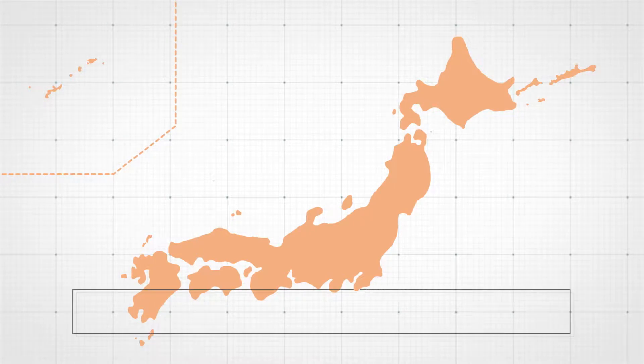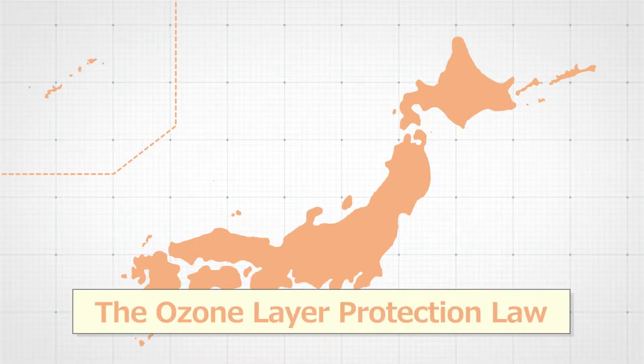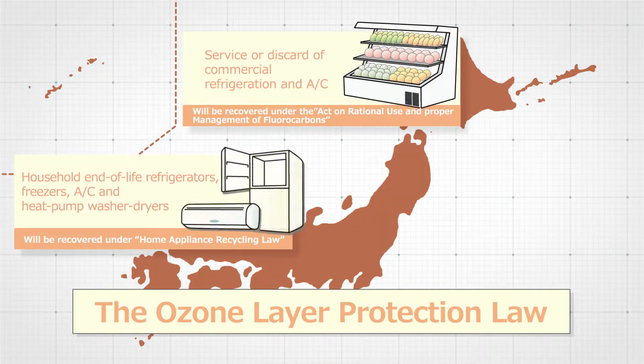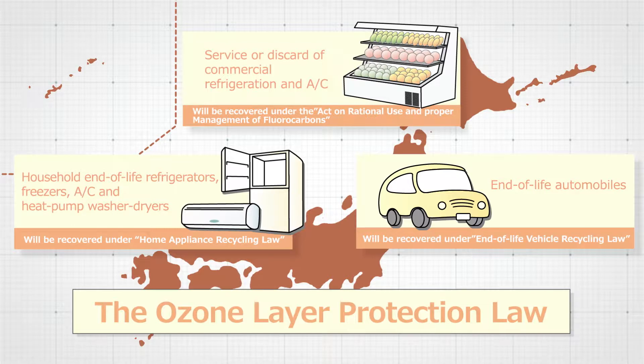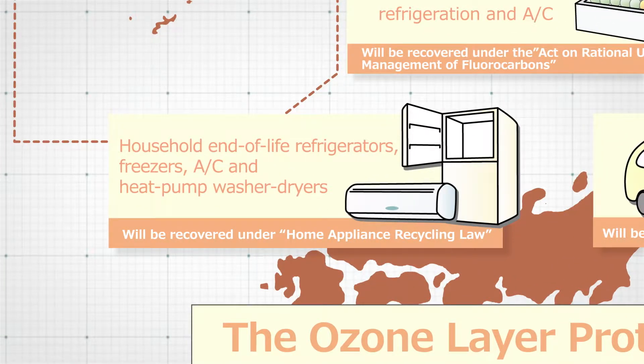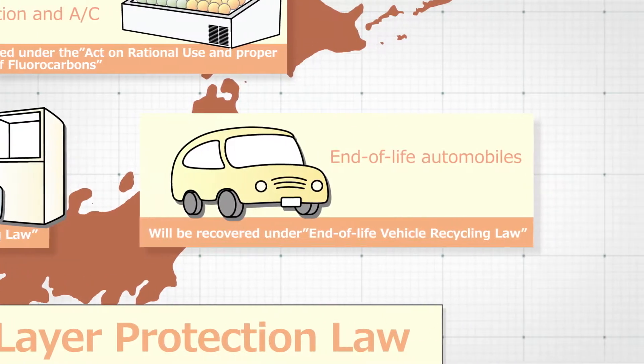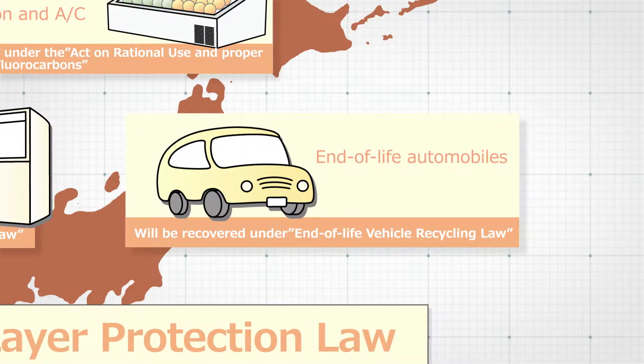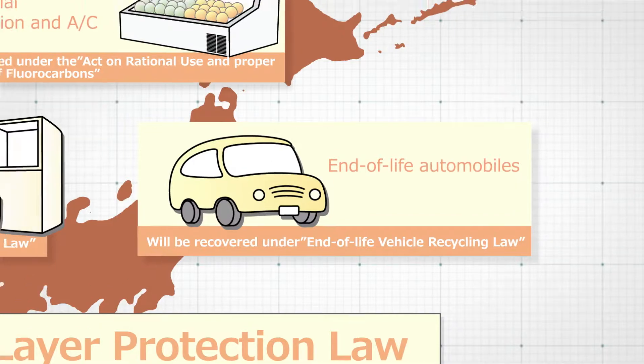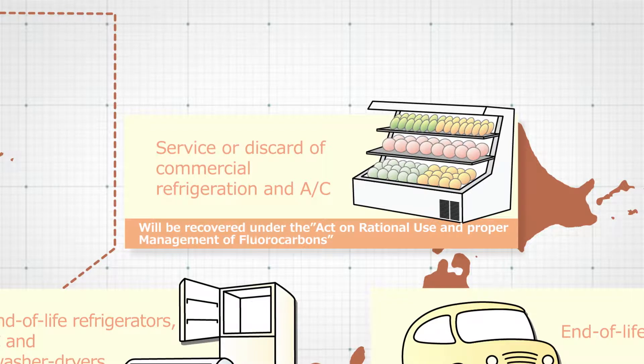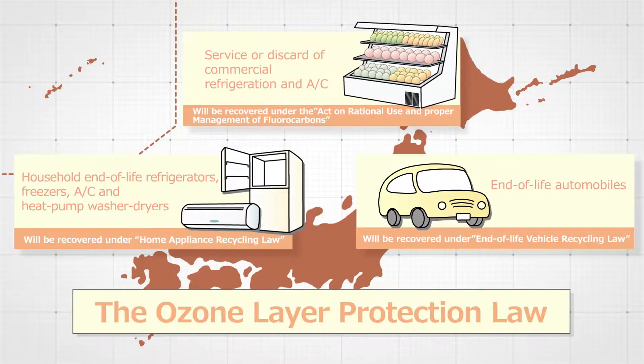As for Japan's fluorocarbon management, the production of ozone-depleting substances is regulated based on the ozone layer protection law. For household air conditioners, refrigerators, freezers, and washing and drying machines, there is a home appliance recycling law. Disposal of automobile air conditioners is regulated under the end-of-life vehicles recycling law. For commercial refrigerators, freezers, and air conditioning equipment, there is a fluorocarbon emission control law. These regulations mandate appropriate recovery of fluorocarbon to prevent its release into the atmosphere.